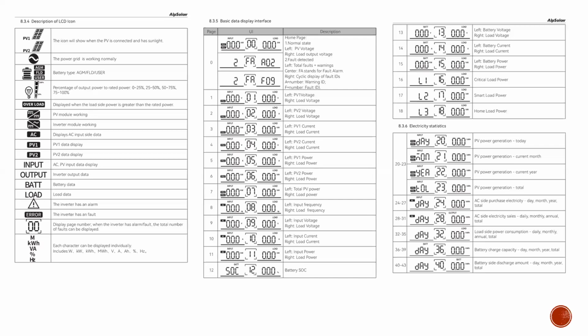So when you move to the other side of the page, you see the basic data display interface. This just shows you the different interfaces that our inverter has. Let's take for example, if you want to check the SOC of the battery on the inverter, you press the down button to page 12 of our S2 inverter. If you are using our 6 kilowatt inverter, you navigate down to page 8. Then you see the SOC of the battery right from the inverter. So this is just the basic introduction to how the display interface of the inverter looks. And then the next thing we have on the next slide is our parameter settings.